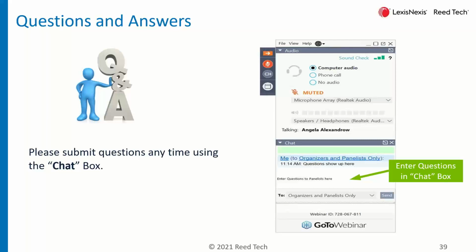Let's see. Is GUDID registration required if UDI is applied to an unclassified device in advance of the September 2022 deadline? I think the answer is yes, right? If you're applying UDI, you should go ahead. Yeah, there's registration. Patti, I think you've had some customers that comply early, right? Oh, absolutely. When they talk about the deadline, you're not prevented from submitting this information early, and it's always a good practice to do so when you're able. So many have submitted their Class 1s early.